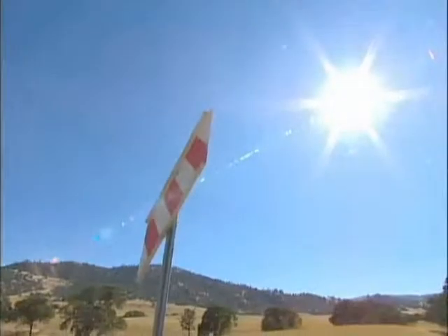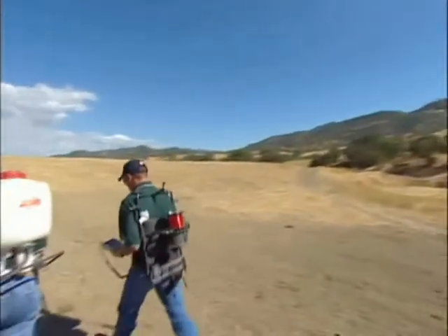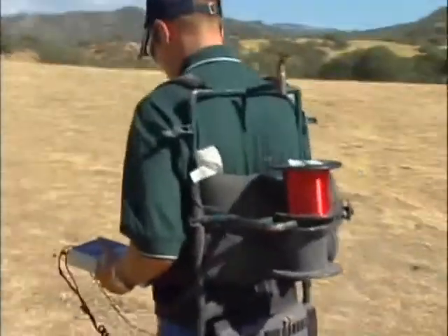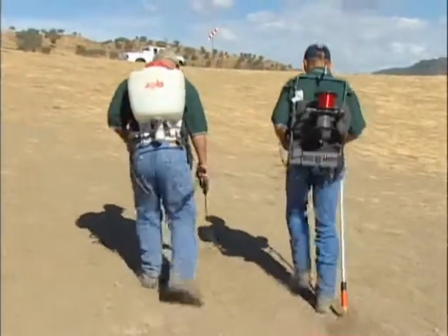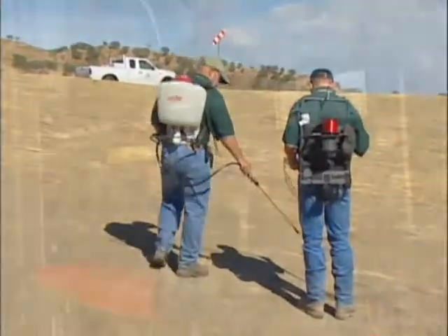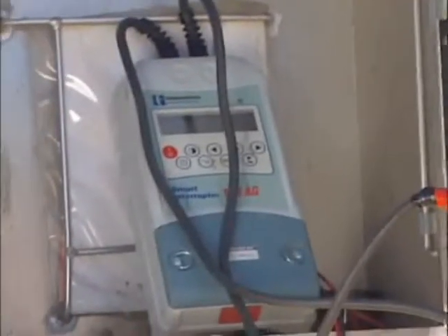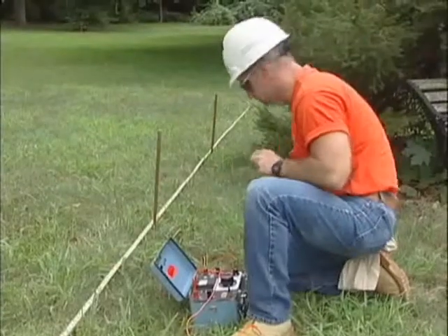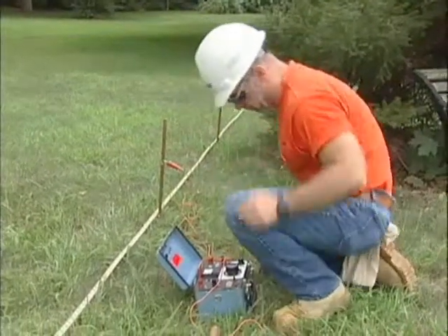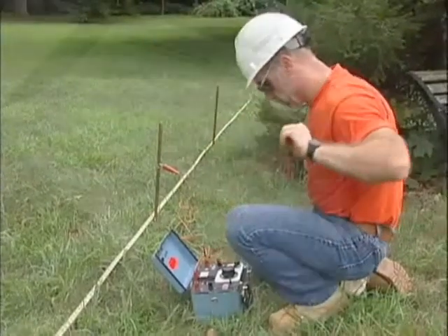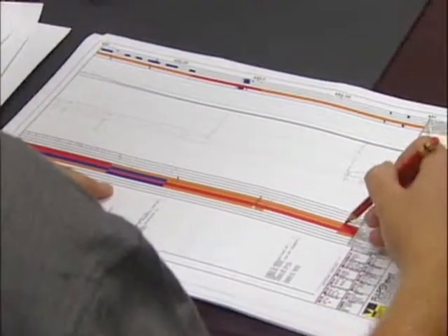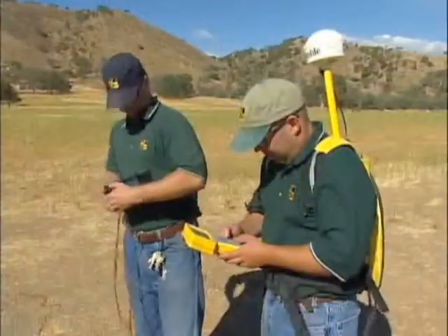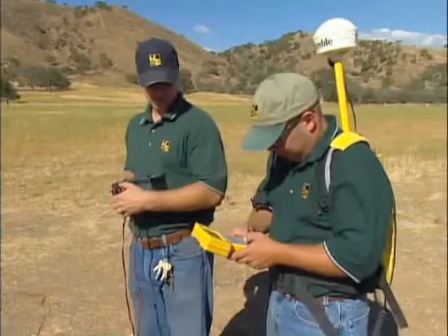To determine the level of cathodic protection, the Close Interval Pipe-to-Soil Potential Survey technique, or CIS, is used. CIS is accomplished by measuring pipe-to-soil voltages, or potentials, at close intervals along the pipeline. On rectified systems, the testing is performed while synchronously interrupting the CP current sources. The corrosivity of the soil around the pipeline can be determined using other techniques, such as the Wenner four-pin method. To ensure that the data collected in the field can be accurately located for subsequent evaluation and potential excavation, many companies use Global Positioning Survey Equipment, GPS, with sub-meter accuracy.